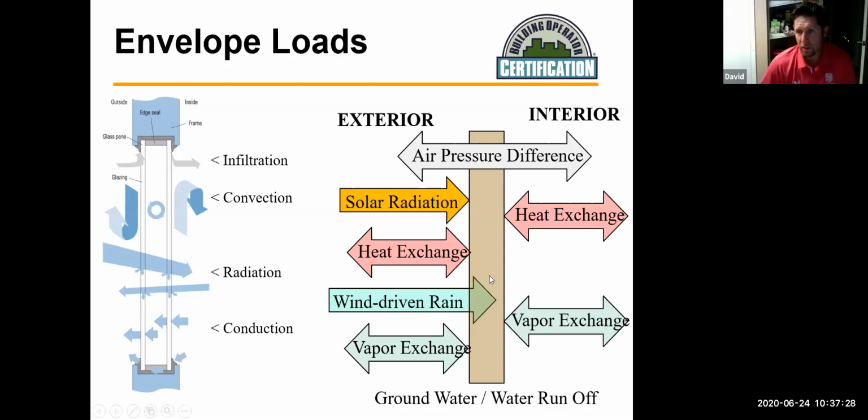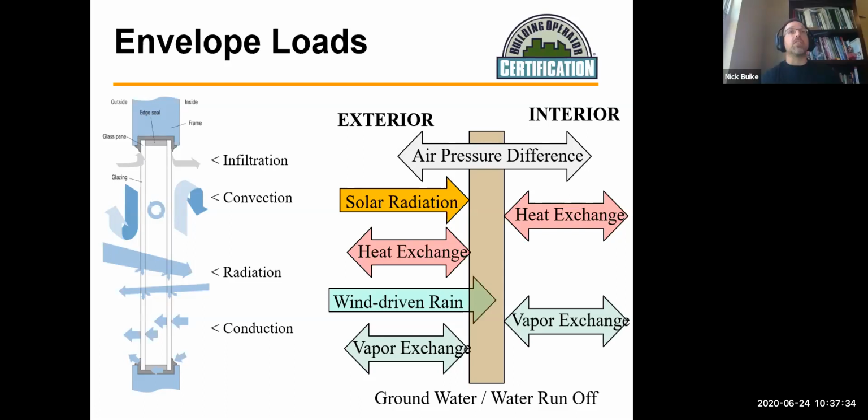All right, so basically the only time you want negative pressure is when you're in some sort of a moisture environment. For the most part, that is correct. Or a lab environment. There's a lot of labs where they'll use air valves and they'll try to maintain negative pressure within certain areas of the building. And not going into a full lab design here, but that's so that you mitigate contaminants from being pushed into the rest of the hallways or the rest of the adjacent spaces.